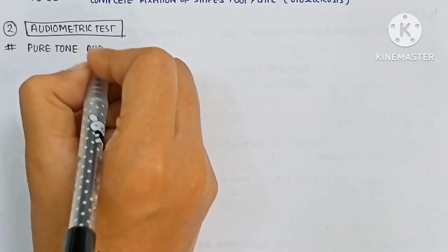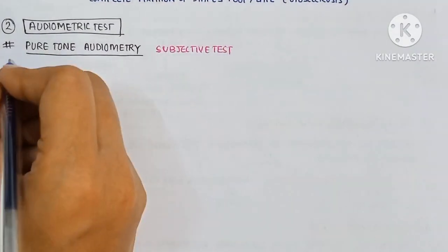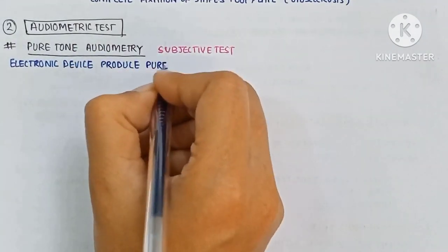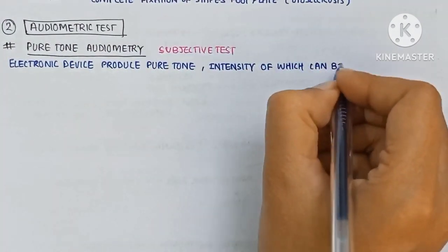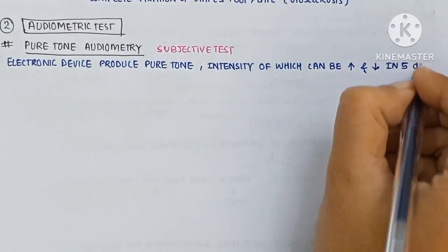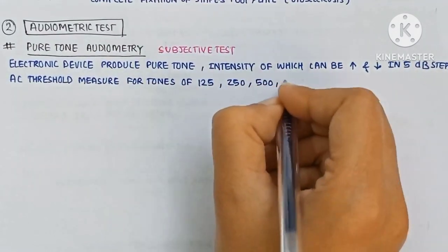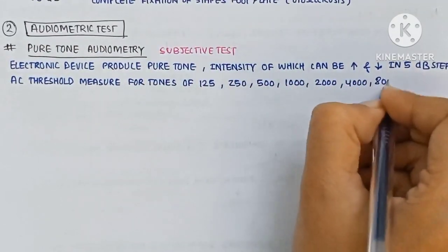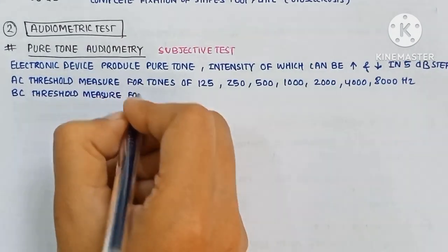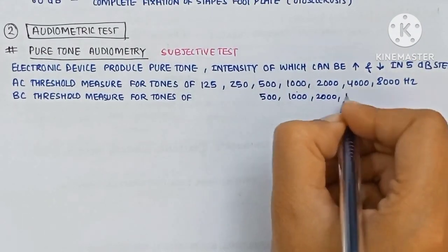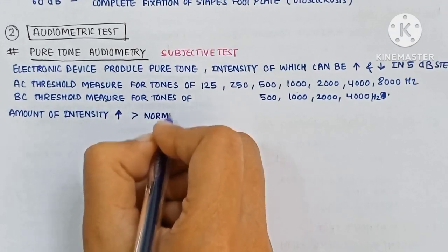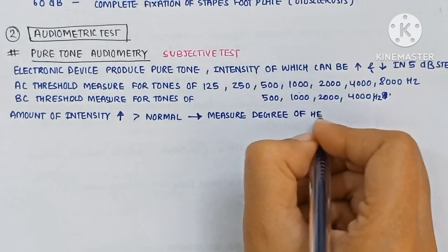First is the pure tone audiometry. It is a subjective test. It is an electronic device that produces pure tones, the intensity of which can be increased or decreased in 5 decibel steps. The AC threshold is measured for tones of 125, 250, 500, 1000, 2000, 4000, and 8000 Hz. The BC threshold is measured for tones of 500, 1k, 2k, and 4k.